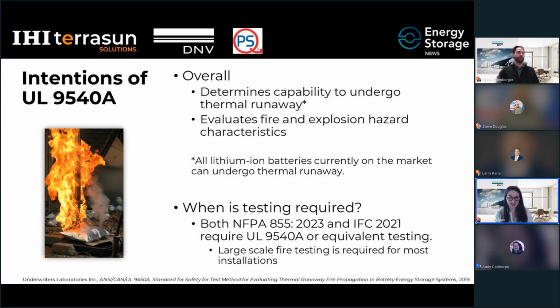So UL 9540A is a test method for evaluating thermal runaway fire propagation in battery energy storage systems. It is currently in its 4th edition, and its overall intention is to assess the hazard characteristics of a BESS that can undergo thermal runaway. It first tests if the basic component of the battery can undergo thermal runaway, and then evaluates the fire and explosion hazard characteristics of that BESS. The test can then be used in a variety of different ways, including informing the design and safety features of the BESS, as well as setting some minimum spacing requirements for battery installations.